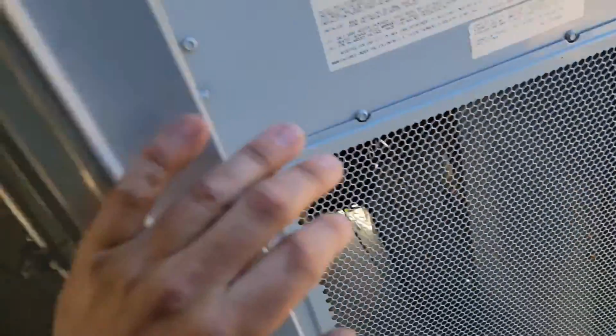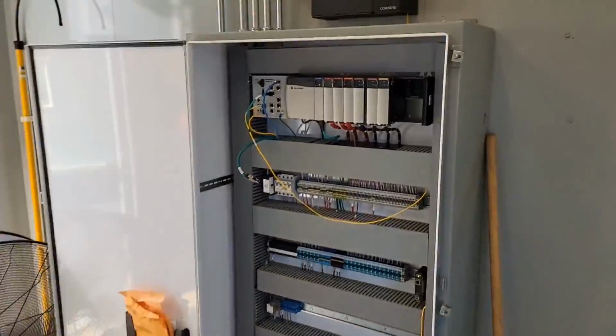Fan's running. Outdoor fan's not running, but the indoor is. Woo! Man, that was a wild goose chase. Cause and effect. We have a reason why that breaker tripped, and now we're waiting for the outdoor fan and the compressor to come on, and we're gonna find out why that breaker tripped.